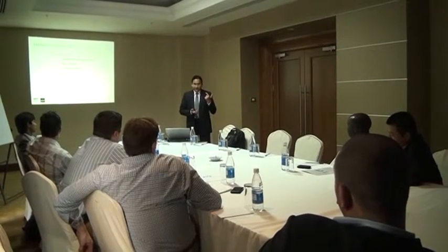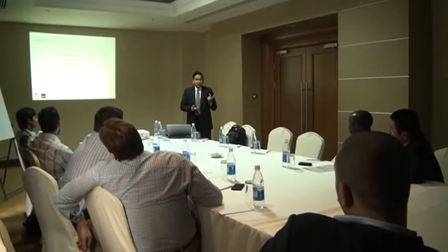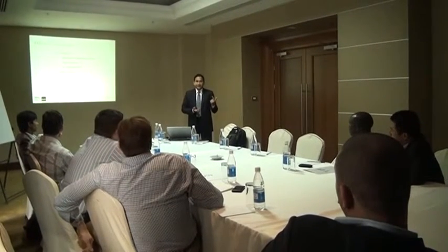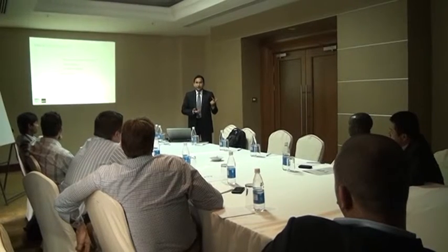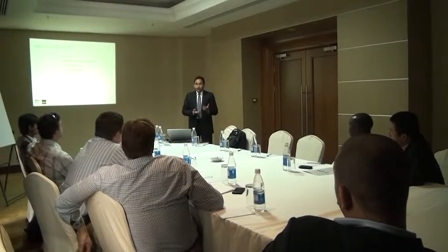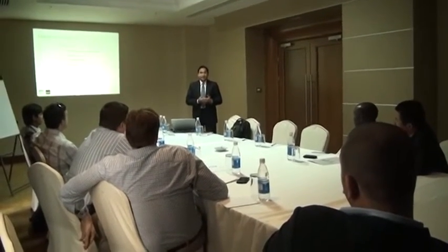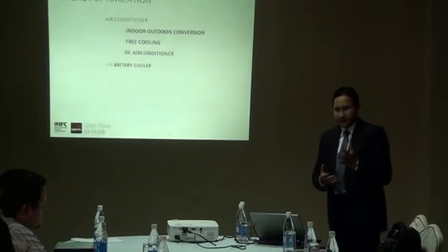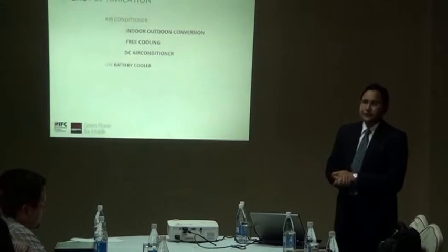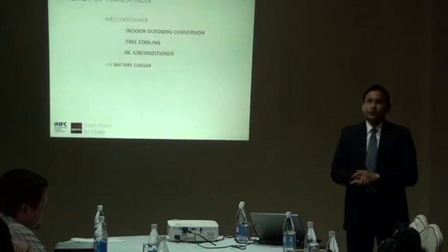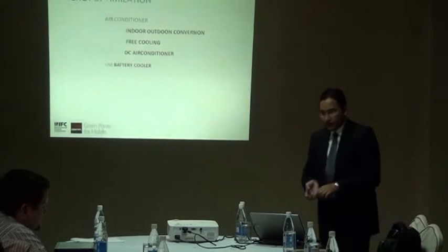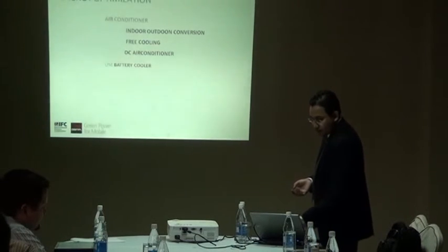Number two, the power requirement is quite low. Even the old battery coolers, which came on the market about 5 years ago, consume about 150 watts, 200 watts. I know for sure the new generation consumes much lower than that, maybe 50% of it. I saw one of the presentations yesterday, and in that presentation the battery cooler was taking much lower power. So this is one of the ways of reducing your power requirement.